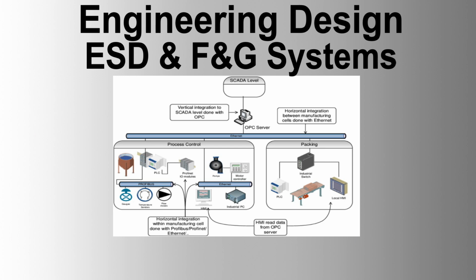2. System robustness. The system must be highly resistant to hardware and software malfunctions. Any single fault within the system should not result in a total shutdown. The ESD system should be designed to be fail-safe, normally energized except for LED lamp output/breaker as appropriate. A 1 logic is the normal state, and a 0 logic signal indicates an abnormal, trip failure state. All I/O modules should be capable of being changed out online without damage or disrupting plant operation.